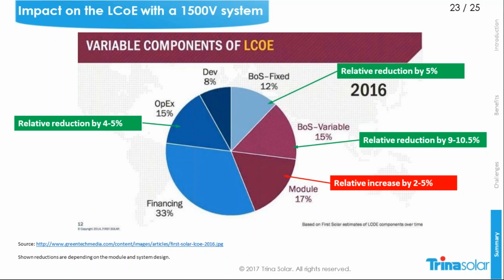On the module side, for the fixed BS cost, it's basically the number of transformers and inverters versus the additional cost. So if you have to buy 4 instead of 5, you have one inverter station less to install, and especially in countries with high labor cost, reducing the installation cost is key to get the best out of the power plant.